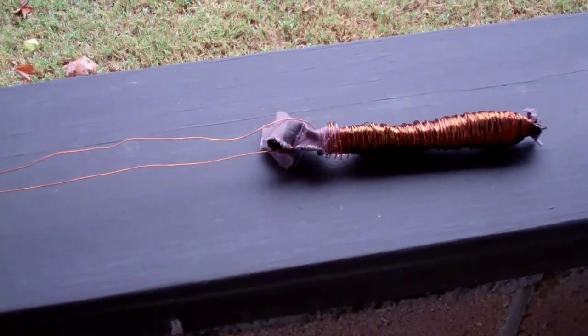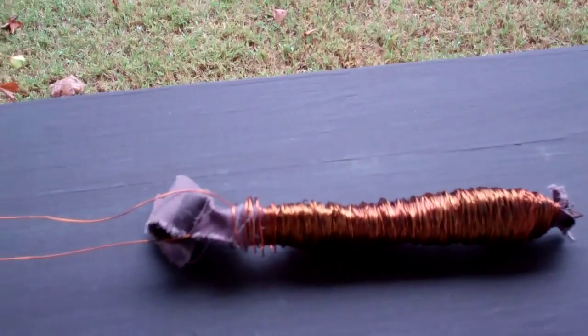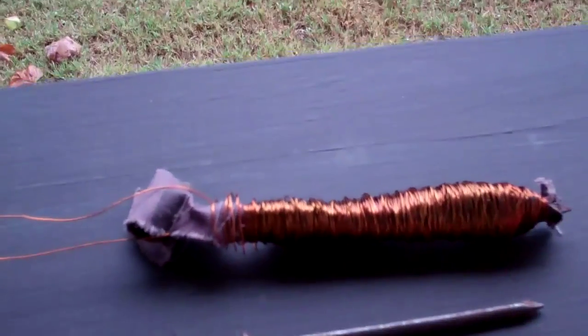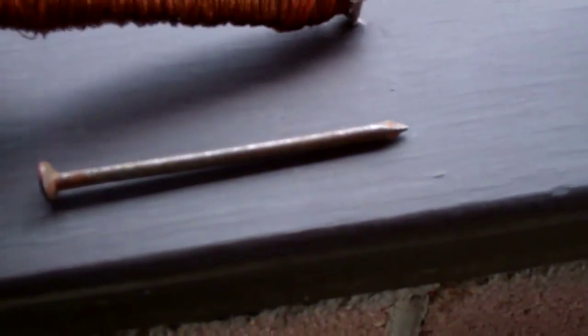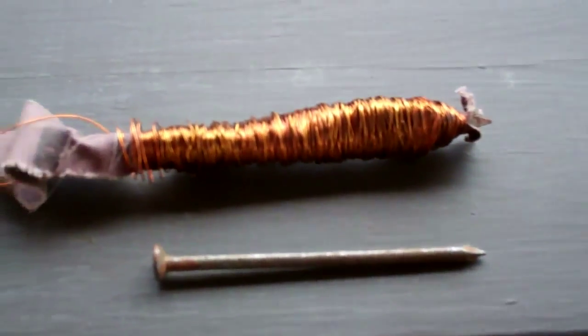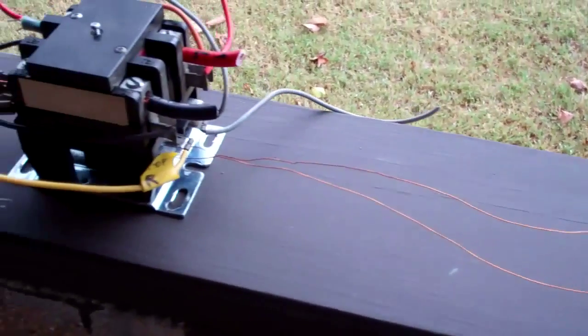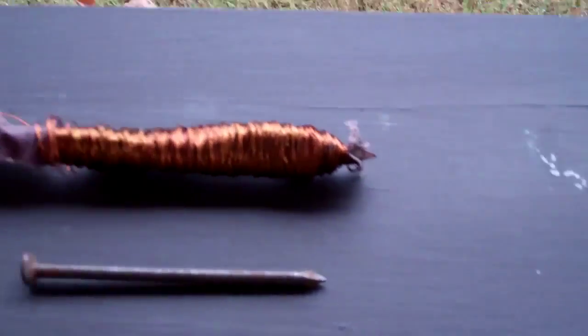We have a wound coil. This is actually wound around emery cloth. It looks like — it's bigger than a 16-penny nail. There's a nail inside of this copper coil here, and this contactor actually worked. This was dangling down below — so this is how I found it.